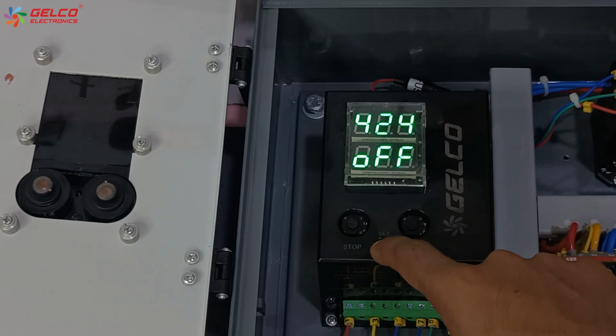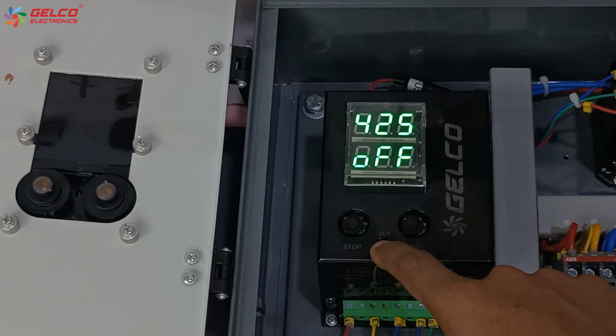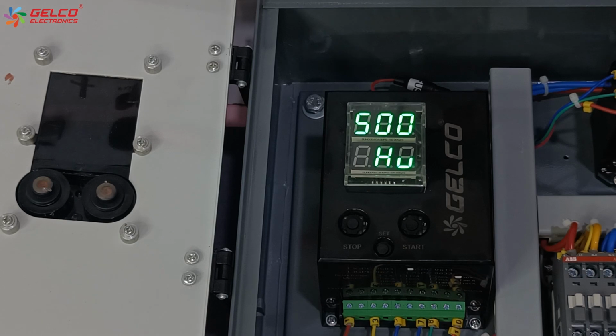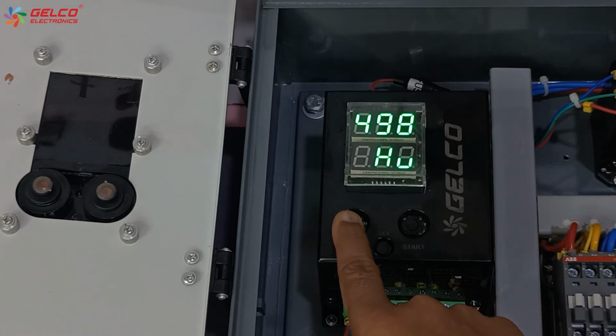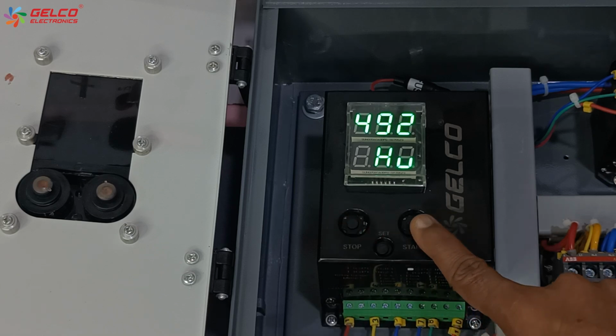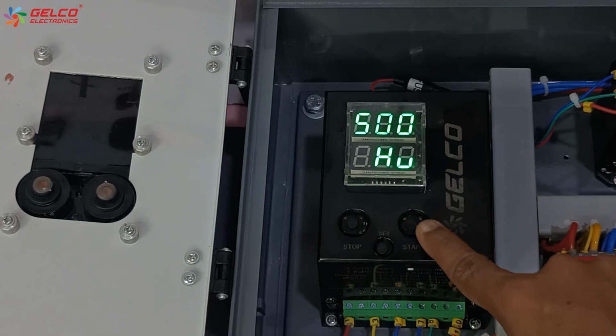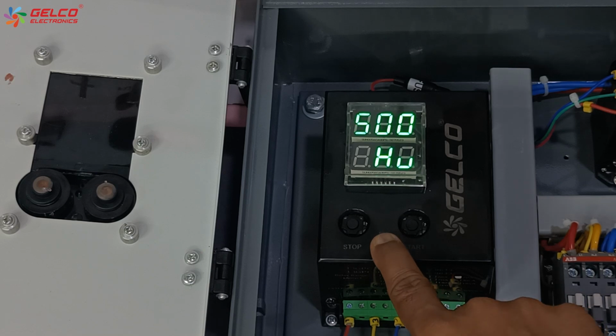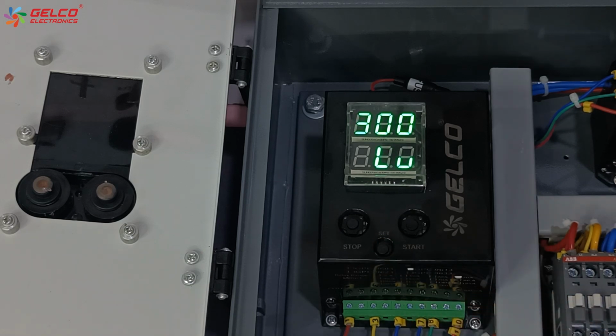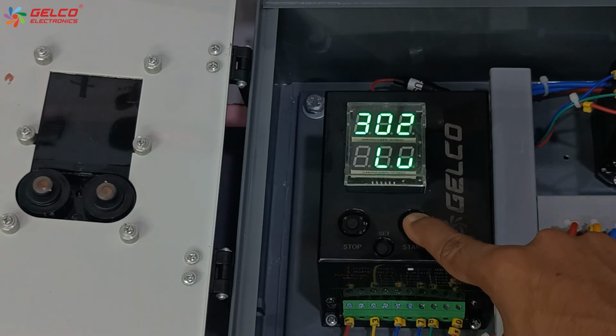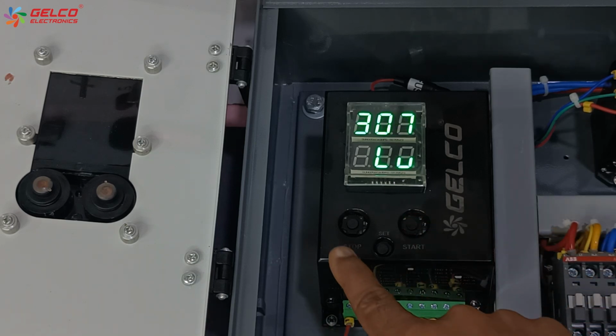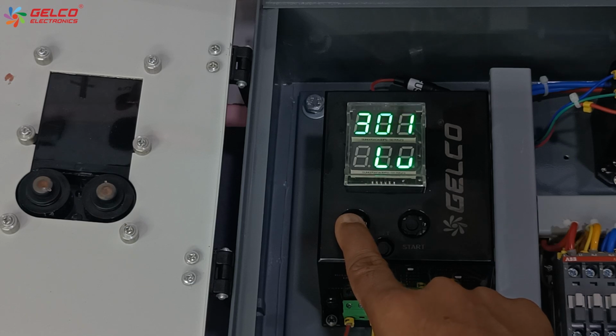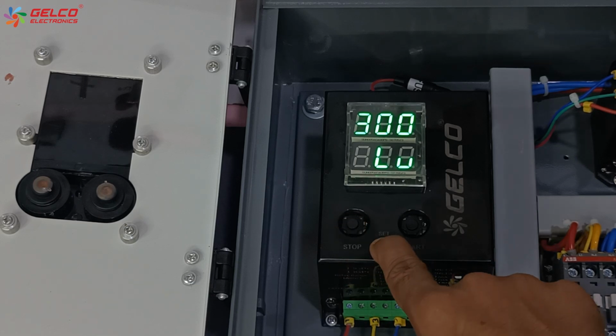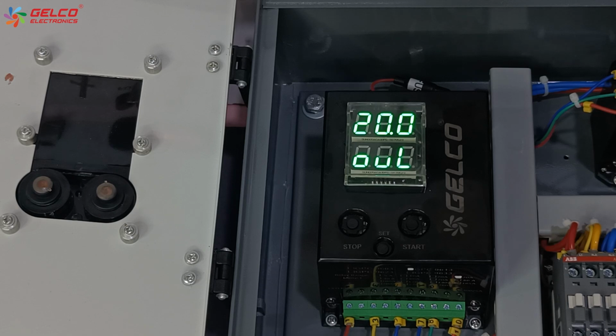Now press the set button for 5 to 7 seconds. Now high voltage option will appear on panel's display. We can decrease it by pressing stop button and increase by pressing start button. Press the set button after the value is selected. Low voltage option will appear on the panel's display. We can increase it by pressing start button and decrease by pressing stop button. Press the set button after the value is selected.